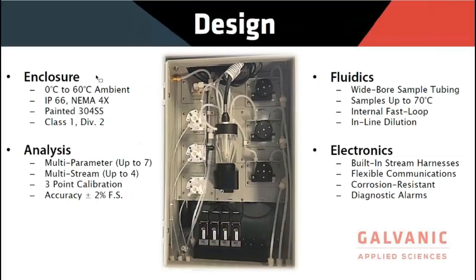For the enclosure, as I mentioned, we can go up to 60 C ambient. The IP protection is 66 NEMA 4X, and the enclosure is painted 304 stainless steel. And this can operate in Div 2 and ATEX Zone 2 areas without a purge. Analyses, multi-parameter. I have calculated it out. I think we can do up to 7 in some special cases. We can do up to 4 streams, and each stream can be multi-parameter, which is another nice feature. 3-point calibration and accuracy and repeatability are all plus or minus 2% full scale.